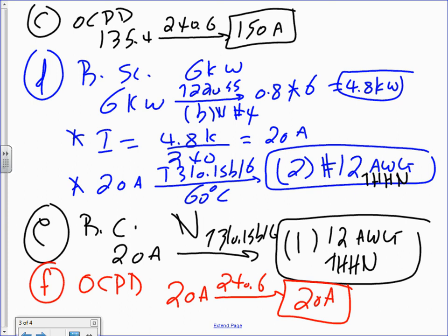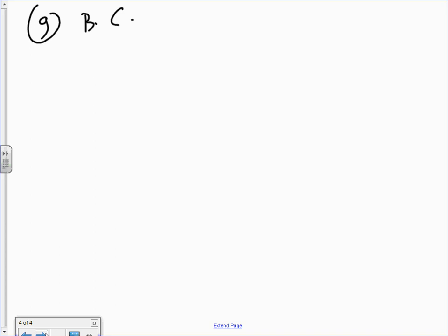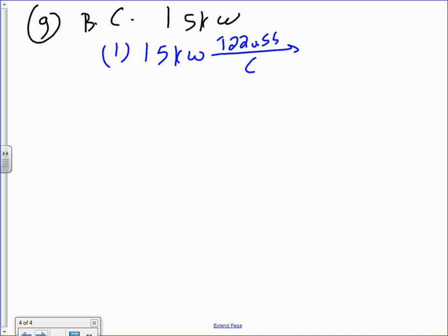Okay. Branch circuit for the 15 kW. Now, from the get-go, Derek, this range is larger than 8 3/4. So, do you derate the neutral for this range? Yes. Can you see that? The neutral will be derated from the get-go. Now you apply the rule for this baby. I have a 15 kW. Take this one to table 220.55, column C. For one range, it will give you 8 kW.